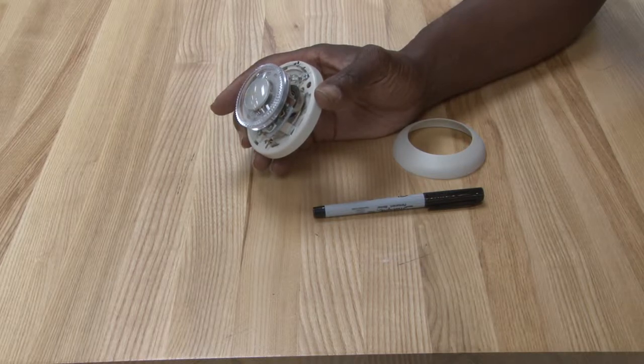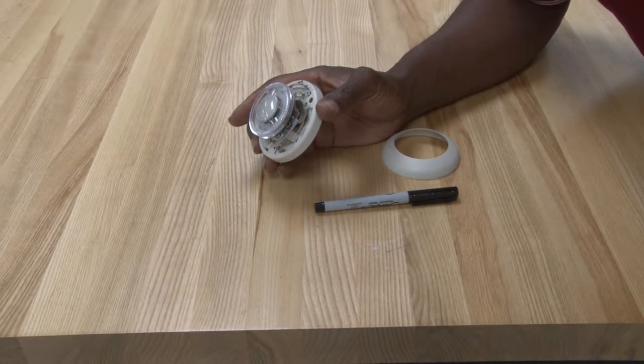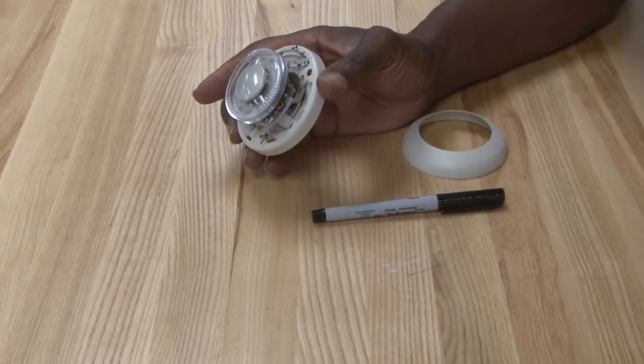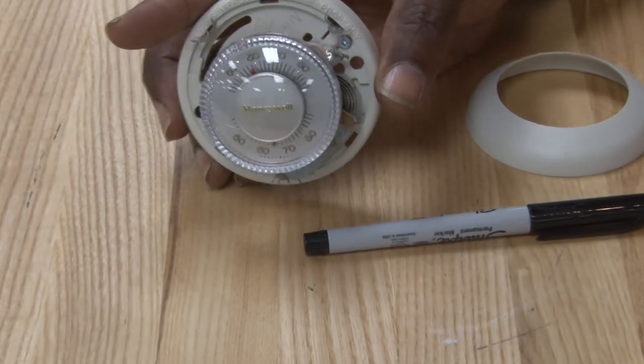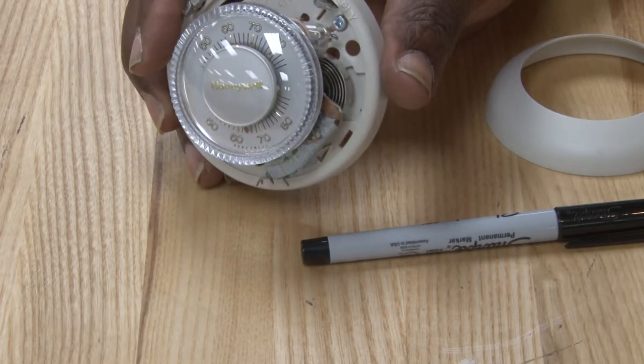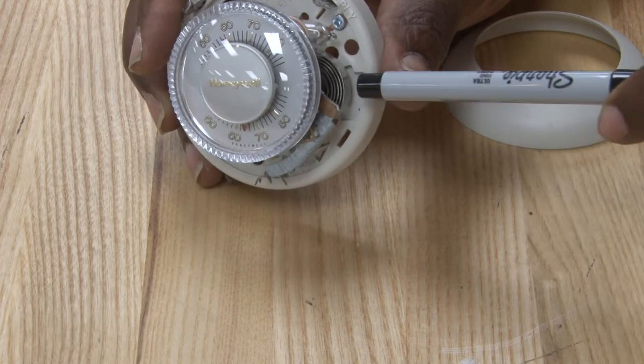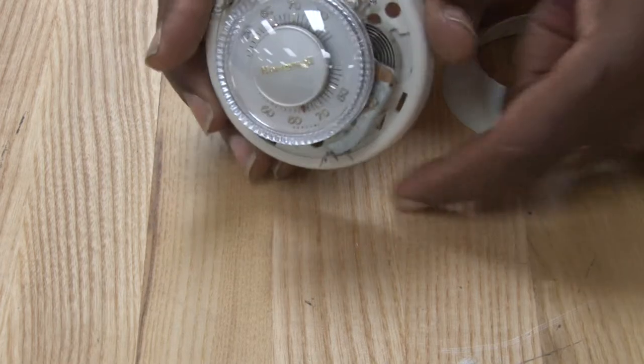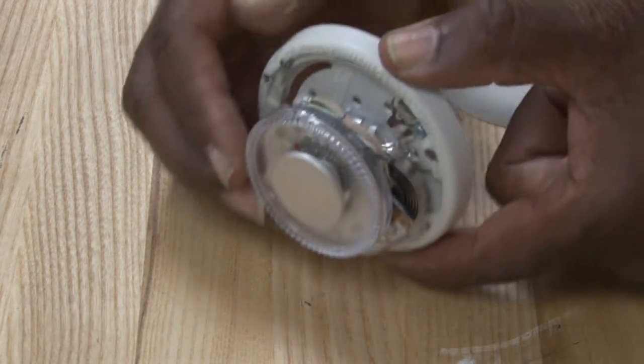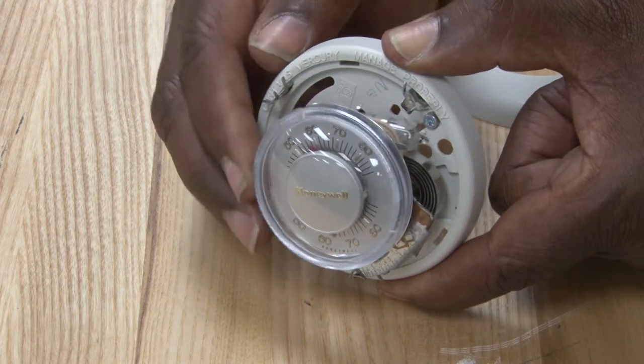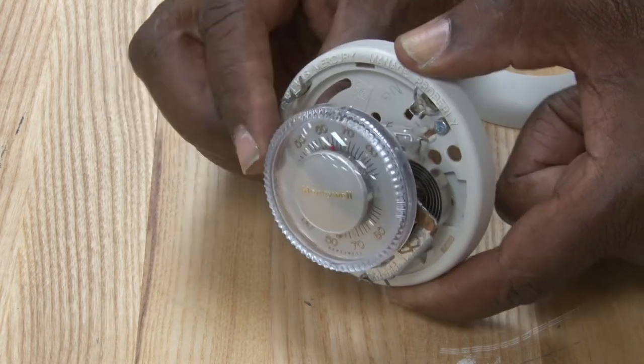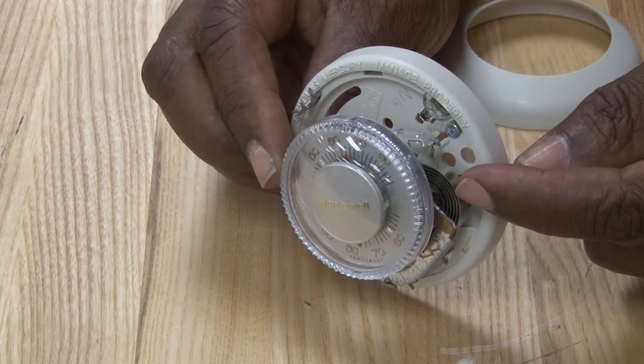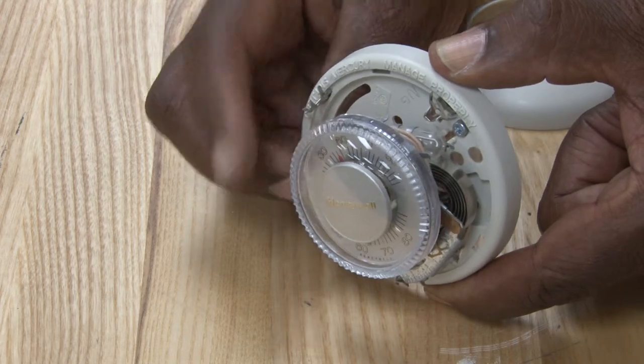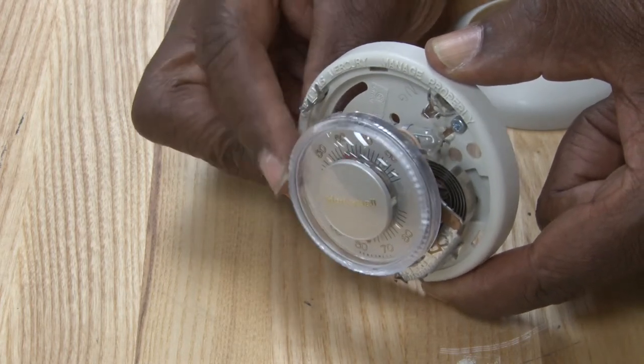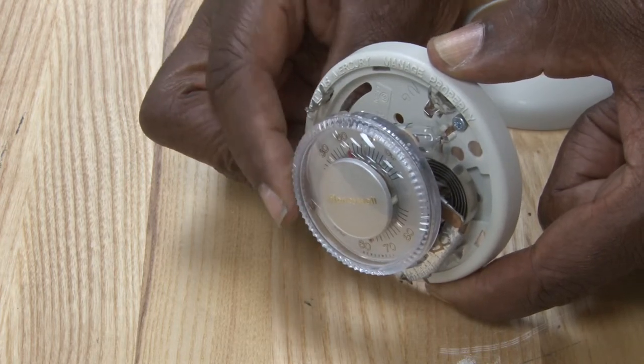So if I could zoom in, we can maybe see the action of... can see the bimetal a little bit better now. The bimetal coil is right there. And if you notice, I'm going to turn the knob, you can see that the mercury is moving and we're causing change in the bimetal coil. But it senses temperature and will cause this mercury bulb to move back and forth to make contact to turn on or turn off the heating and cooling system.